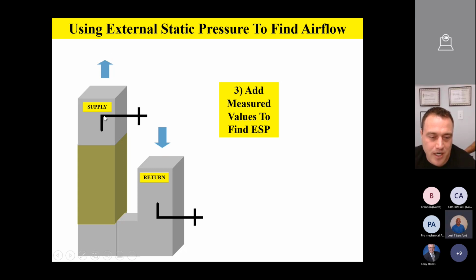Like if the blower was on the bottom. So on the supply side, if you got your fan here and your coil here, you're going to be reading supply side pressure. Now, one of the things I like. After the coil. Well, yeah, go ahead. What he's saying is all of the air handlers are negative because the blower's on top. That's why they're confused.